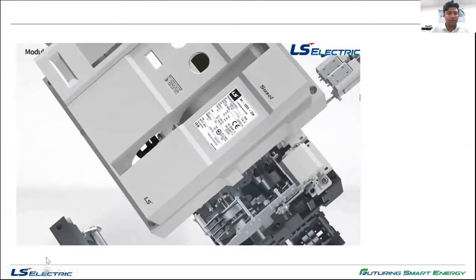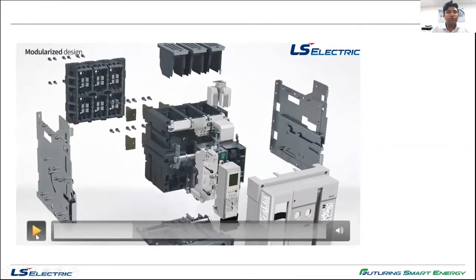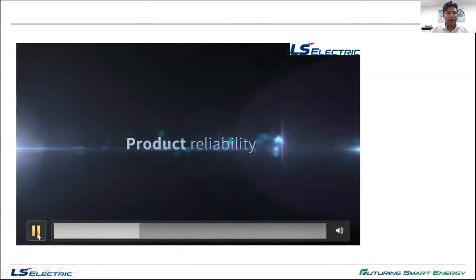Now moving forward, you can see that all our air circuit breakers are of completely modularized design. It means all the components can be dismantled, which means servicing and maintenance are very simple. You can see from the video, there is a moving contact and an arc chamber, different types of accessories, the trip relay and the trip relay base, as well as the covers, etc., and the cradle. So it is a completely modularized design, which means there are no welded parts outside. This allows easy access to all the accessories and maintaining the ACB as and when required, even at the site.